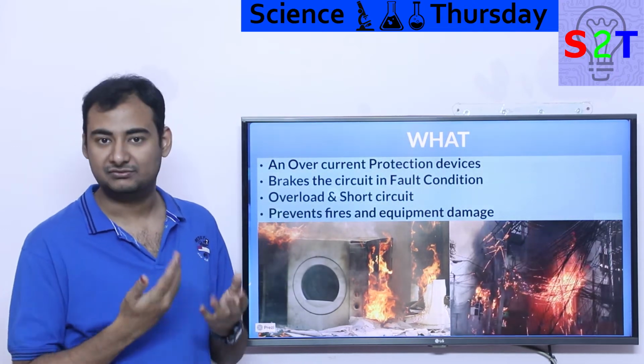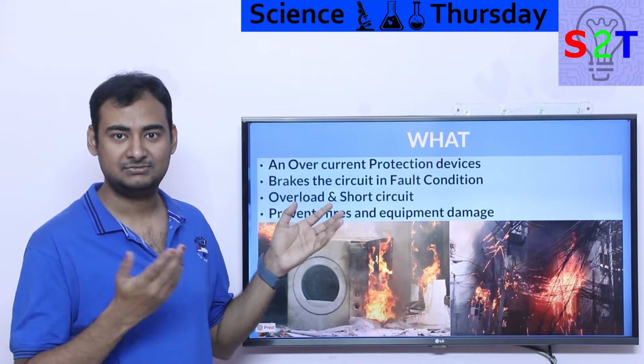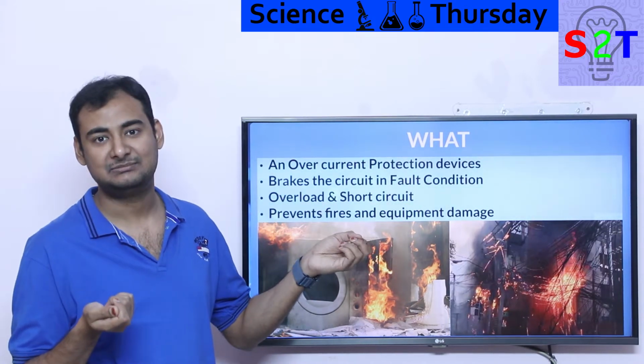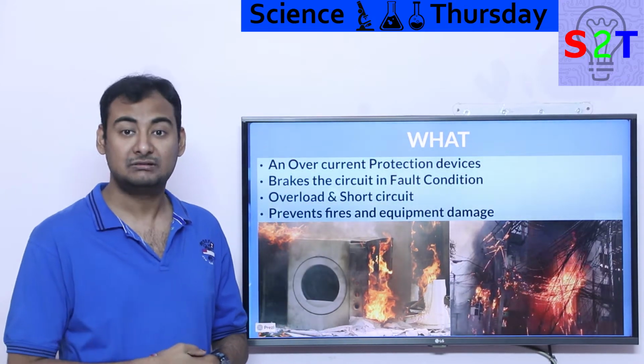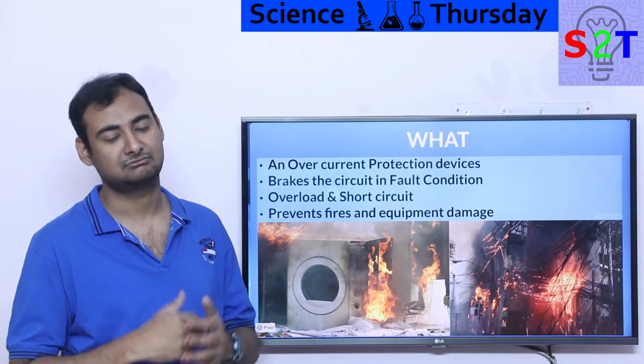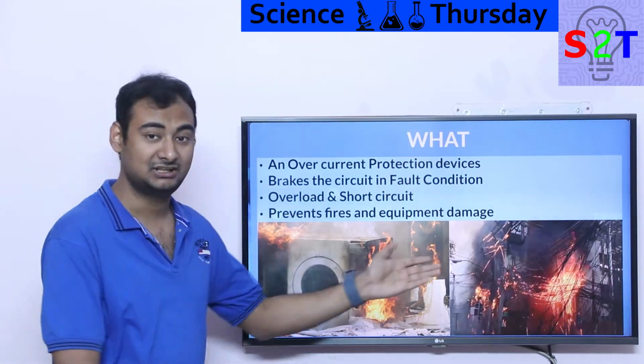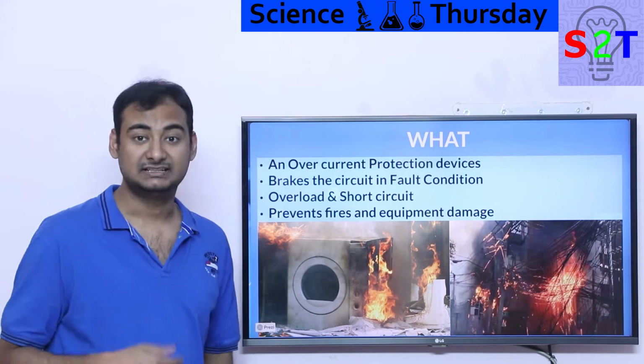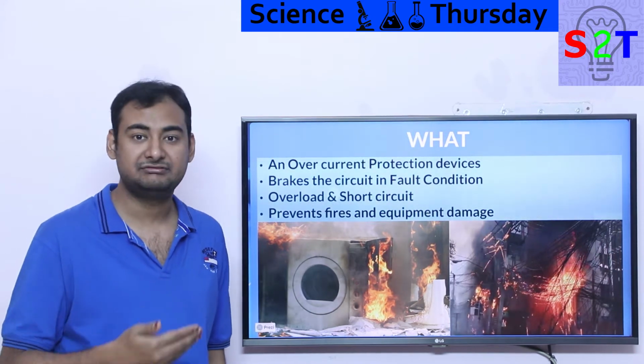So randomly over time you realize your building is burning. Why? Because that electrical wire, designed to handle 10 amperes, now has 12 amperes drawn out of it — it overheated and caught fire. This has happened with multiple equipment setups. That's an overload scenario, because it can happen without you realizing it.